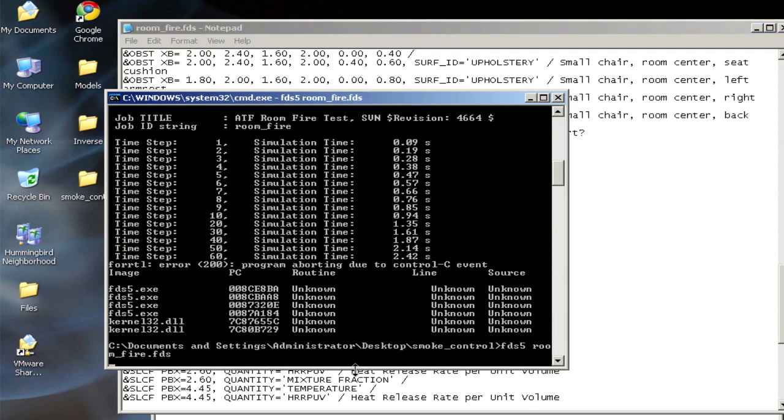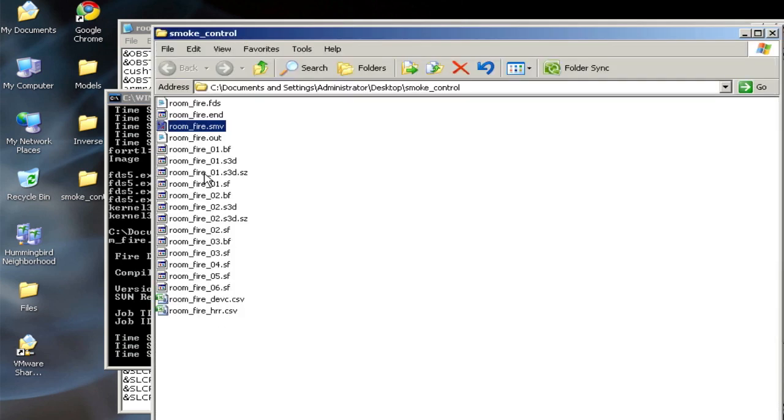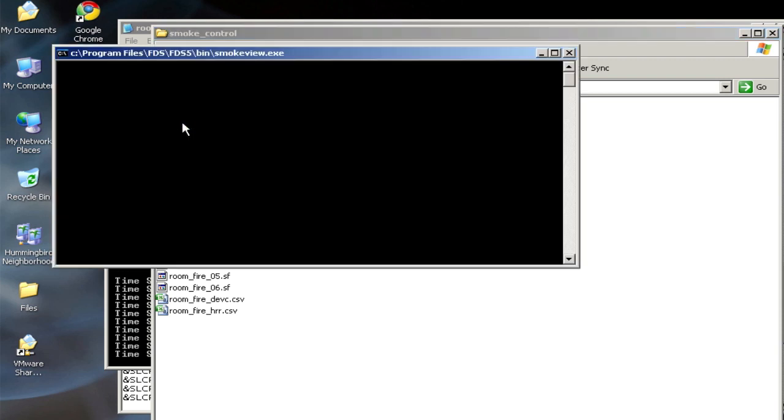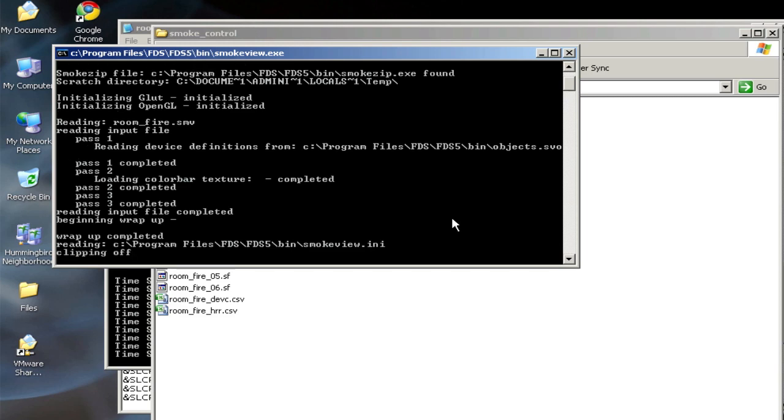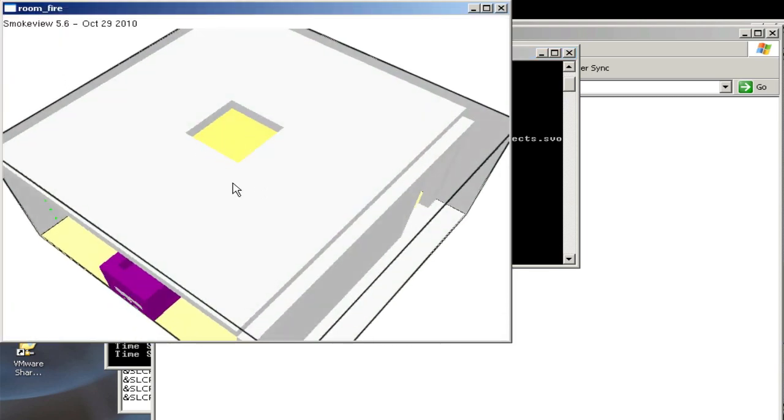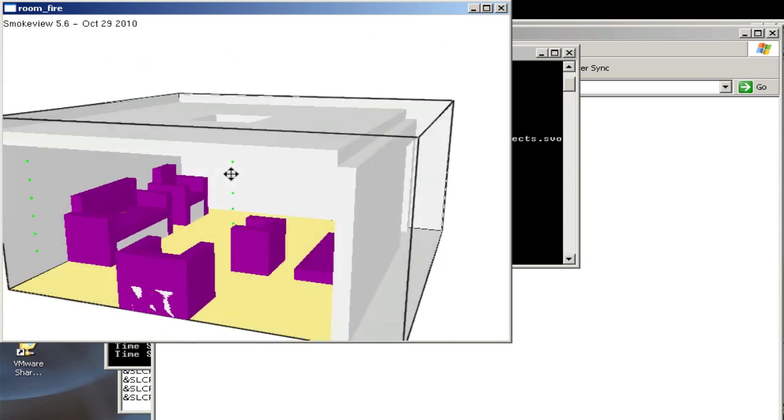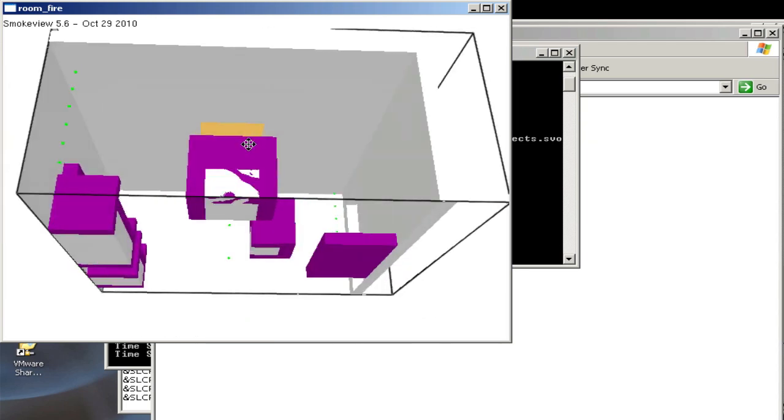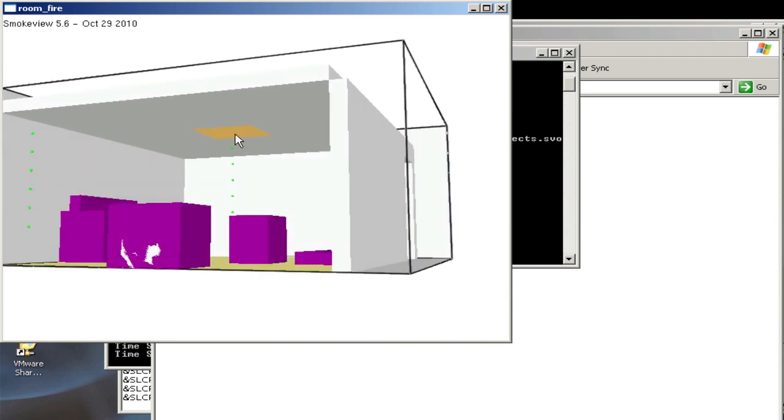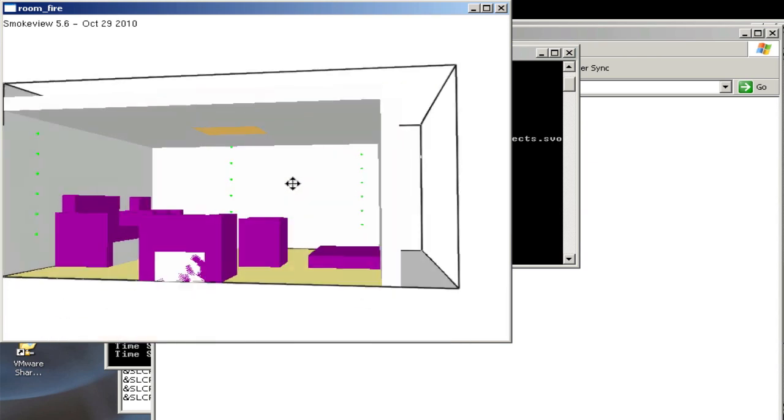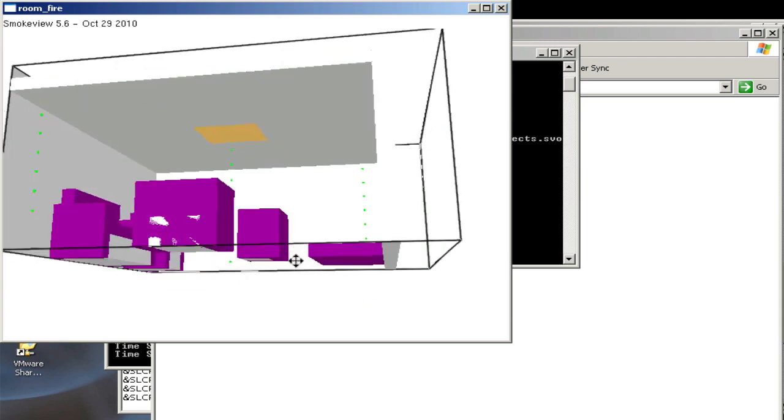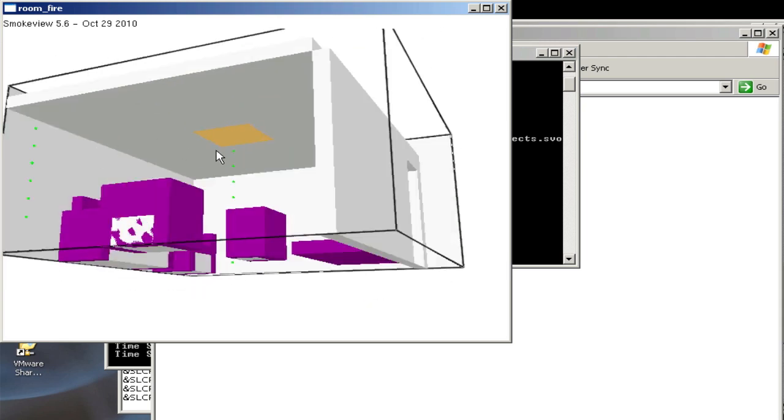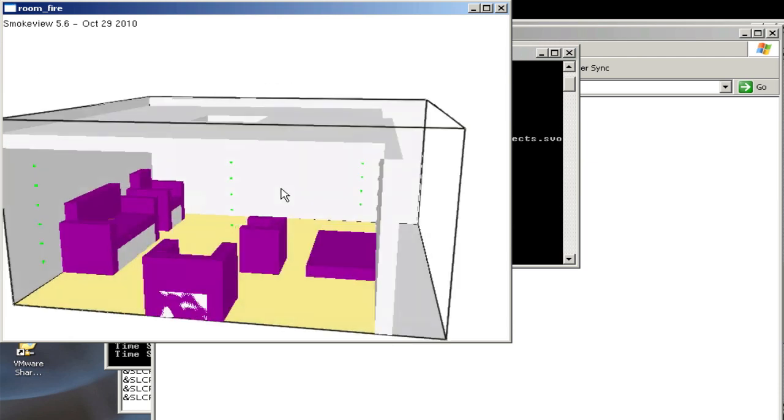And what I should see is a zero cell thick obstruction on the top blowing. So if I open this up in Smokeview now, I should see the hole as before. And now I see kind of a tan color default obstruction. And at first glance, it may look like that's blocking the flow. But since we set it to porous equal true, we're going to allow air to pass through there. And we'll put in some devices and outputs so we can look at the flow. But for now, that's all we need to do. And we'll have a fan from time zero that's going to blow one meter per second in the upward direction. So it's extracting air from our room fire case.